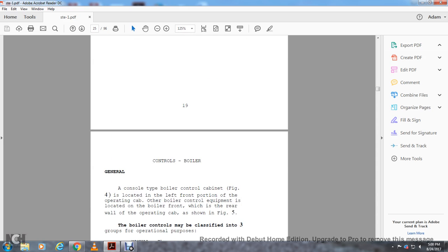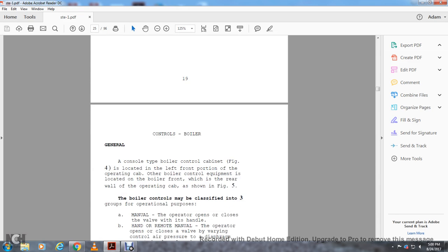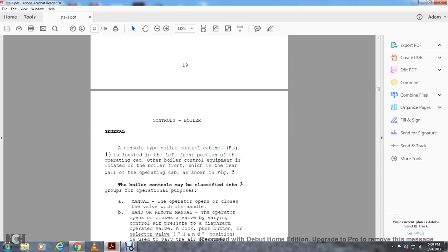Alright, so controls, boiler, general. The console type of boiler control cabinet, figure 4, is located in the left front portion of the operating cab. The boiler control equipment is located on the boiler front, at the rear of the wall of the operating cab, shown in figure 5. The boiler controls may be classified into three groups for operating purposes. Manual: the operator opens and closes the valve by hand. Remote: the operator opens and closes the valve by varying the control air pressure, with a diaphragm-operated cock, a push button or a selector valve.